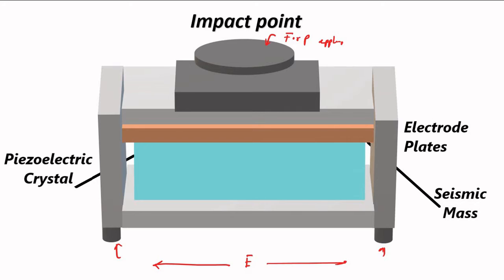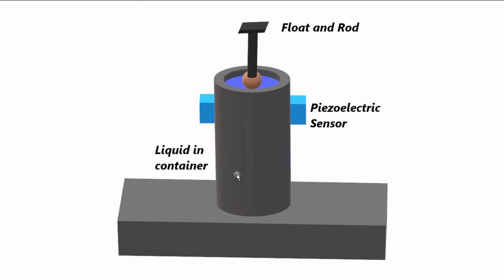Now, how can we use it for level measurement? The basic principle is that we have a container with liquid at a certain level. To sense the liquid level, we place a float and attach a rod with a specific design so that when it moves up and down, its ends strike the impact point of the piezoelectric sensor. When it strikes the impact point, these sensors are triggered and give us a voltage output — a signal indicating the float's current position, which gives us information about the liquid level.